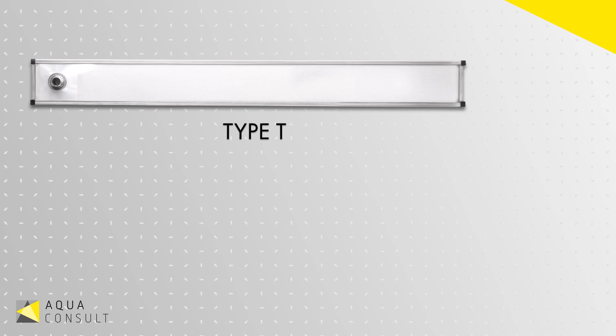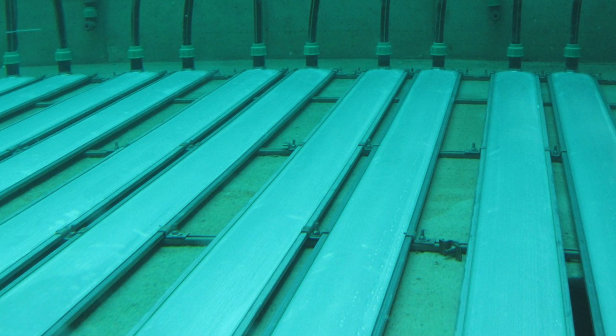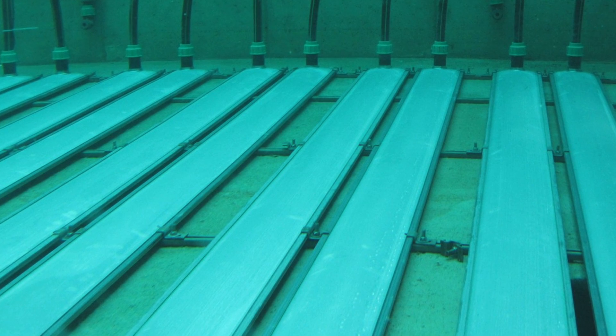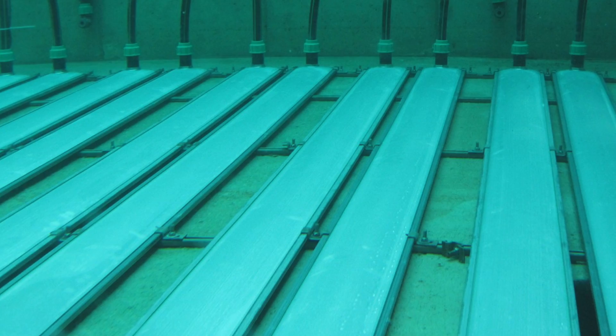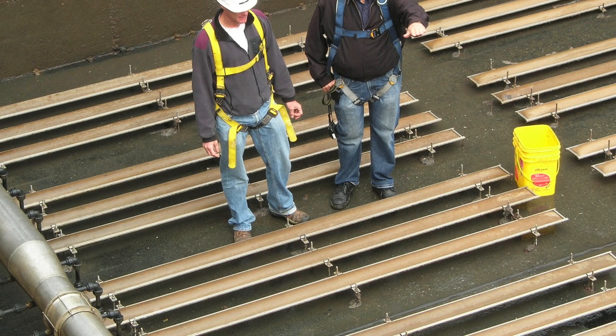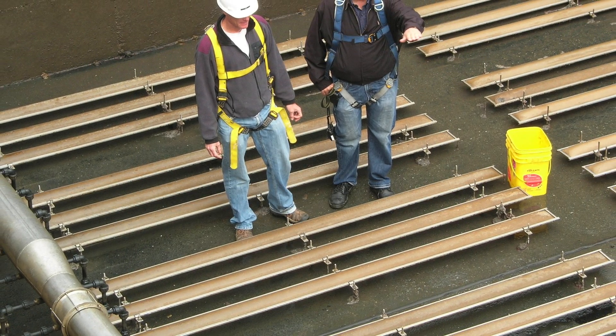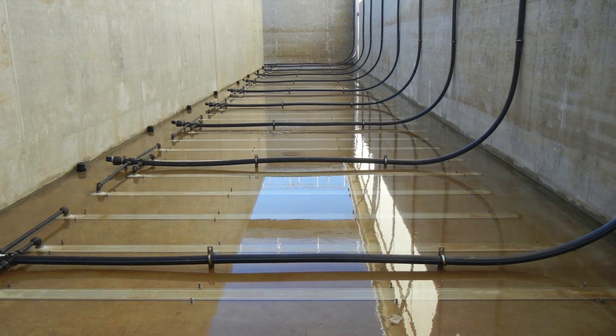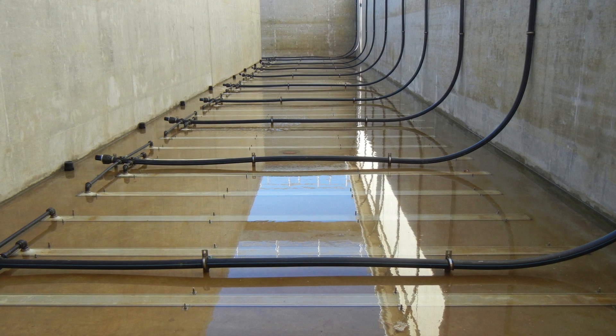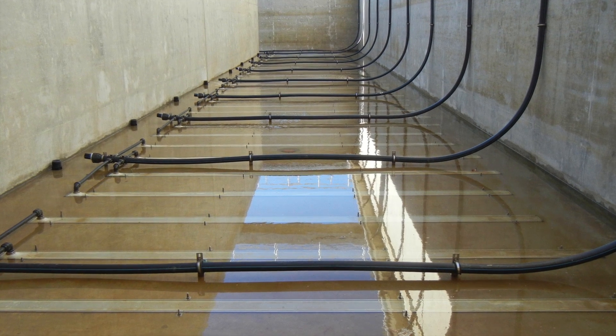The Aerostrip fine bubble diffuser can come in a few different varieties. There's the type T unit that consists of a 316 stainless steel base and a proprietary long-lasting polyurethane membrane. The air connection on a type T is an upward pointed threaded stainless steel connection.